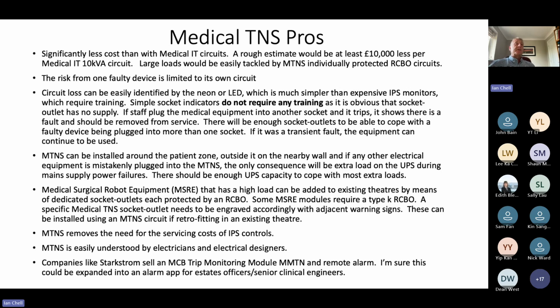Now, MTNS can be installed around the patient zone. They could even be outside of that patient zone on a nearby wall. And if any other equipment is plugged into it, it's no big issue in terms of load, except if there was a power failure, that non-medical device is then consuming load during the actual power failure. But it's not such a risk as before with medical IT.